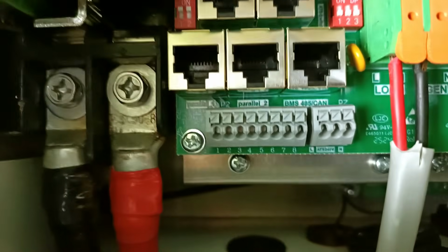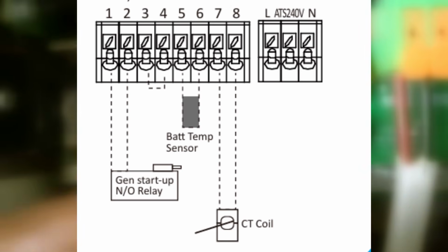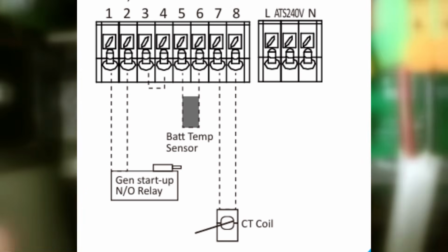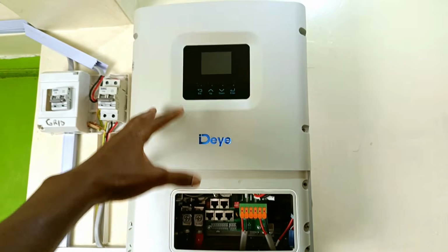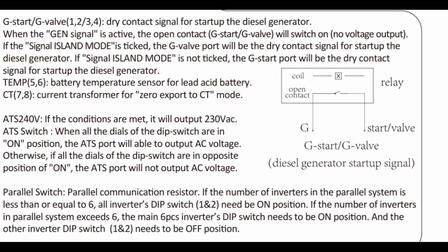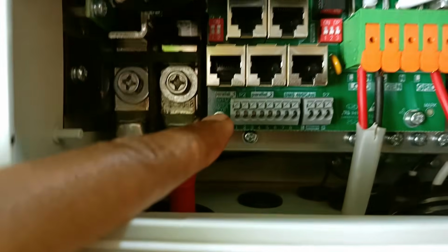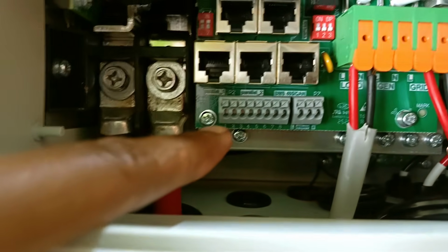Now let's talk about the function ports here. From the left, number 1, 2, 3, and 4 are for connecting a generator. This inverter has the ability to turn on the generator. For example, if there's no solar input, the grid is down, and the battery is low, then this inverter can actually turn on a generator. And you do the appropriate installation by utilizing ports 1, 2, 3, and 4.